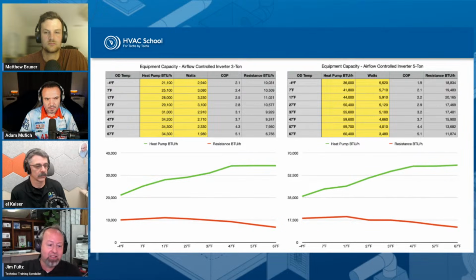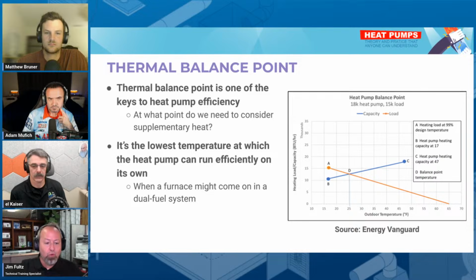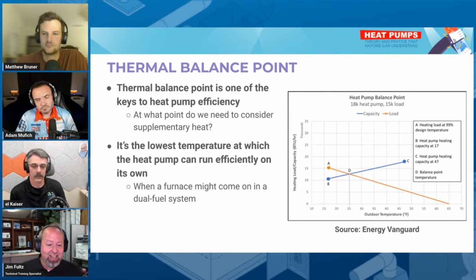But Eric's taken this to another level by showing us what the resistance BTU heat is, which would compare the actual efficiency of the unit. And that COP is dealing with our efficiency of how efficient the heat pump is versus the backup heat. And so capacity would be another level of, if you have enough capacity when you're getting down to 17 or well below the capacity of that heat pump.